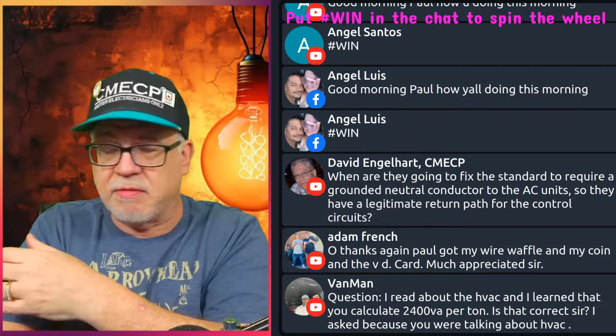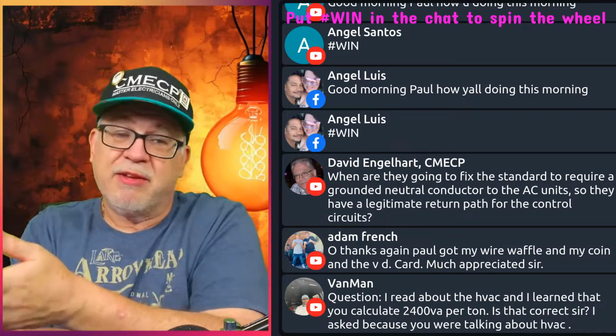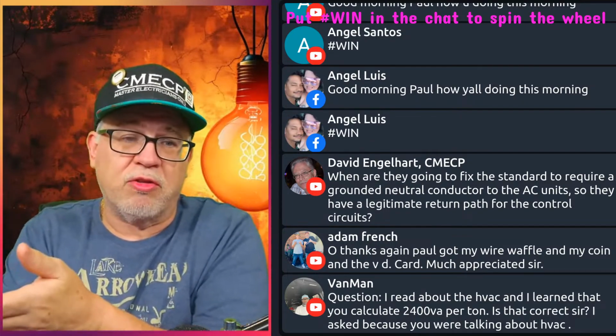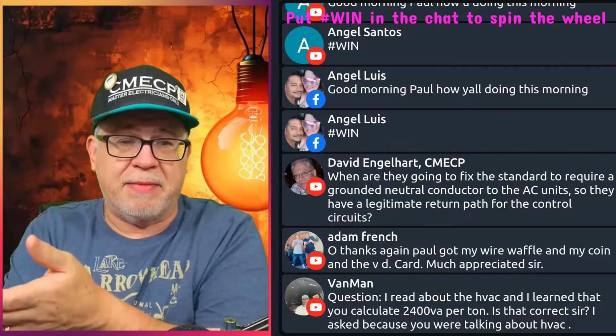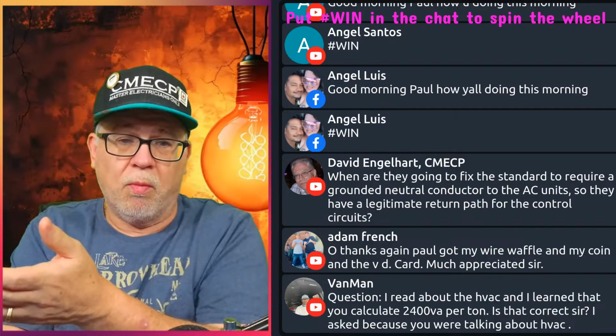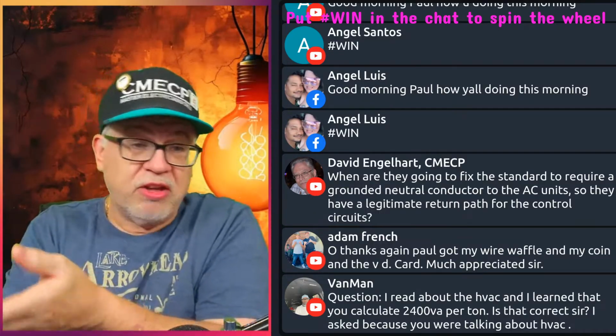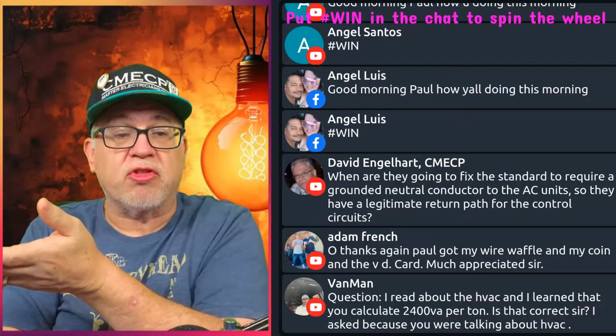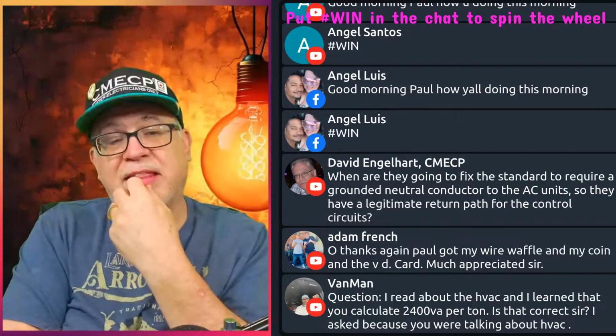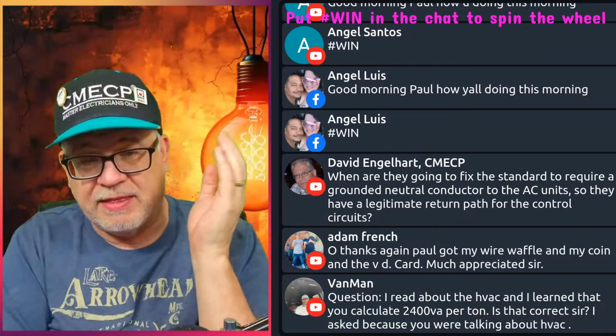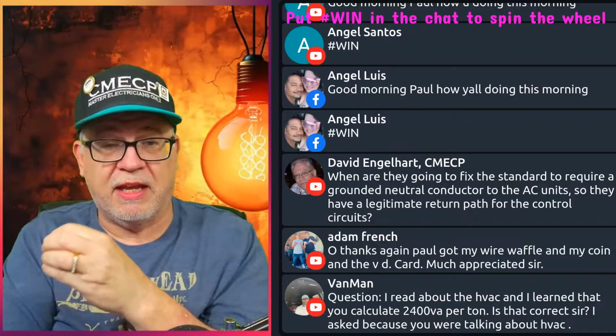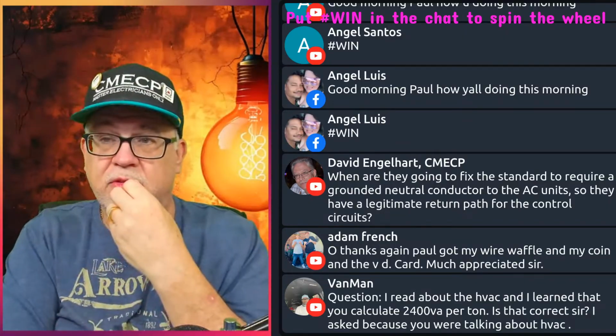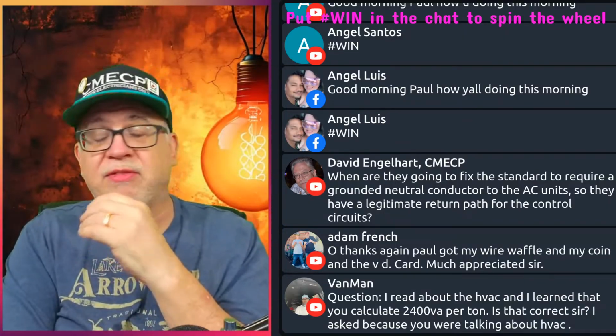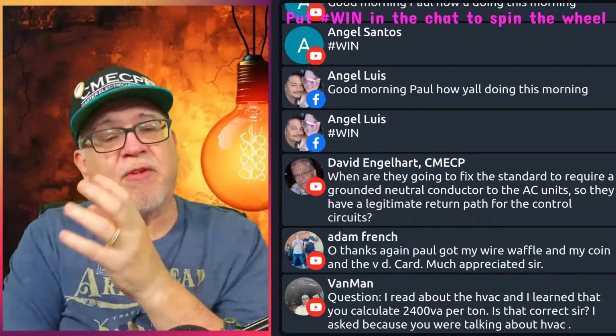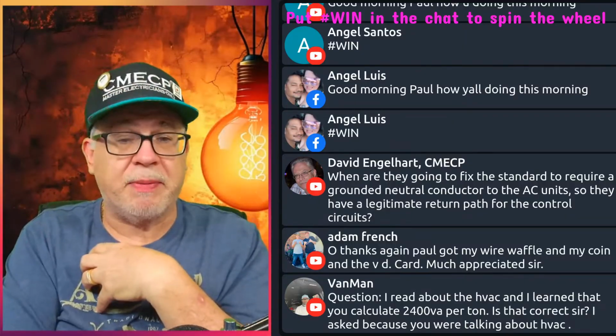And so, again, the milliamp, that's why, let's face it, we know that those HVAC units are tripping because of that 5 milliamp in the inrush. So their solution is, let's just bump it up to don't exceed a 20 milliamp. The problem with that is we've educated everybody that the personnel protection is Class A. 20 milliamps falls more, even though it's called special purpose, it falls more to me into the Class B range.